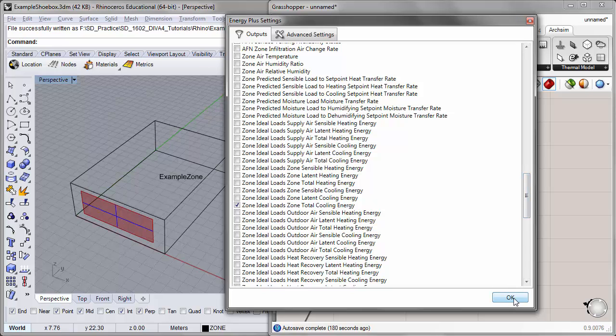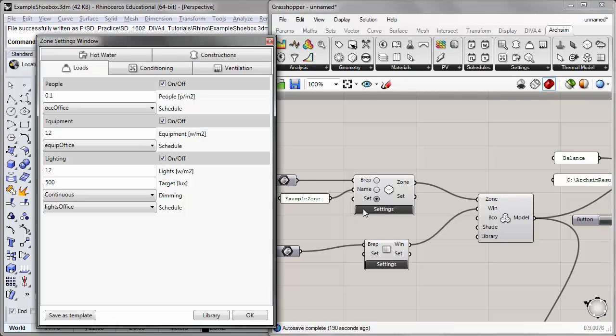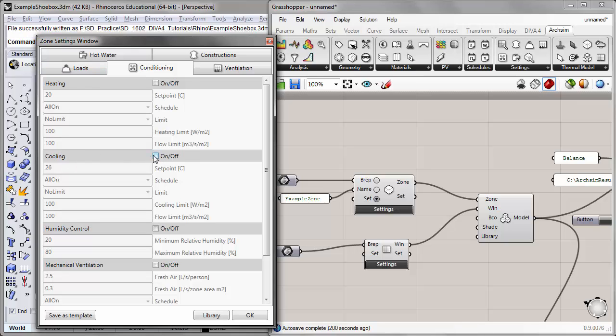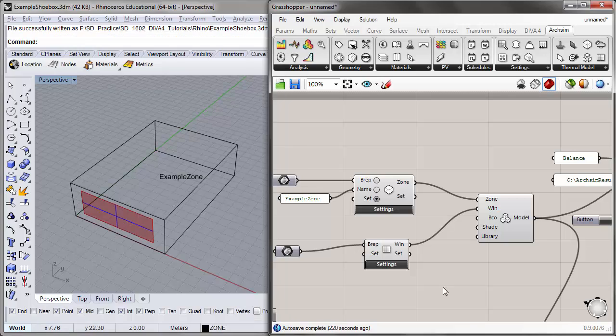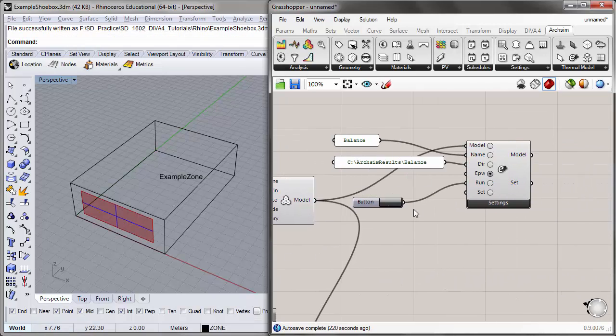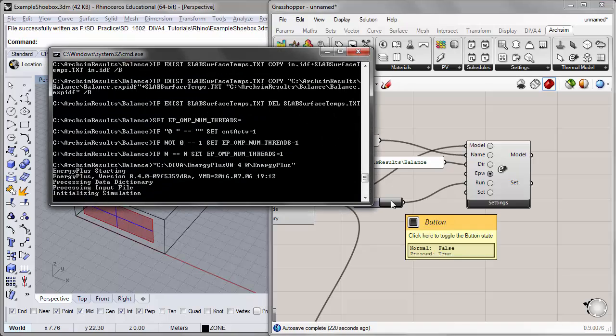I'll press OK. Because I clicked zone ideal loads total cooling energy, I'm going to turn the cooling on just for this simulation to get a sense of the balance. So I'll go over to conditioning and cooling and click cooling. Now that we've selected cooling and have the zone ideal loads total cooling energy selected as an output, it will show us the amount of energy needed to maintain the 26 degree Celsius temperature set point inside our space. I'll click OK and run the simulation, then take a look at the CSV output when it's done.